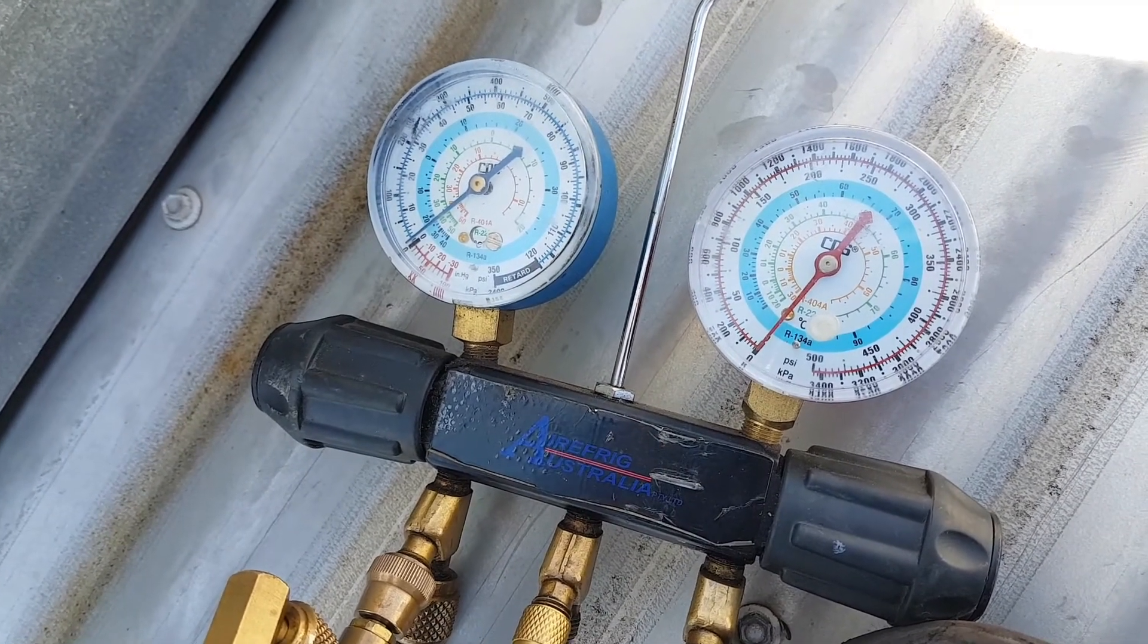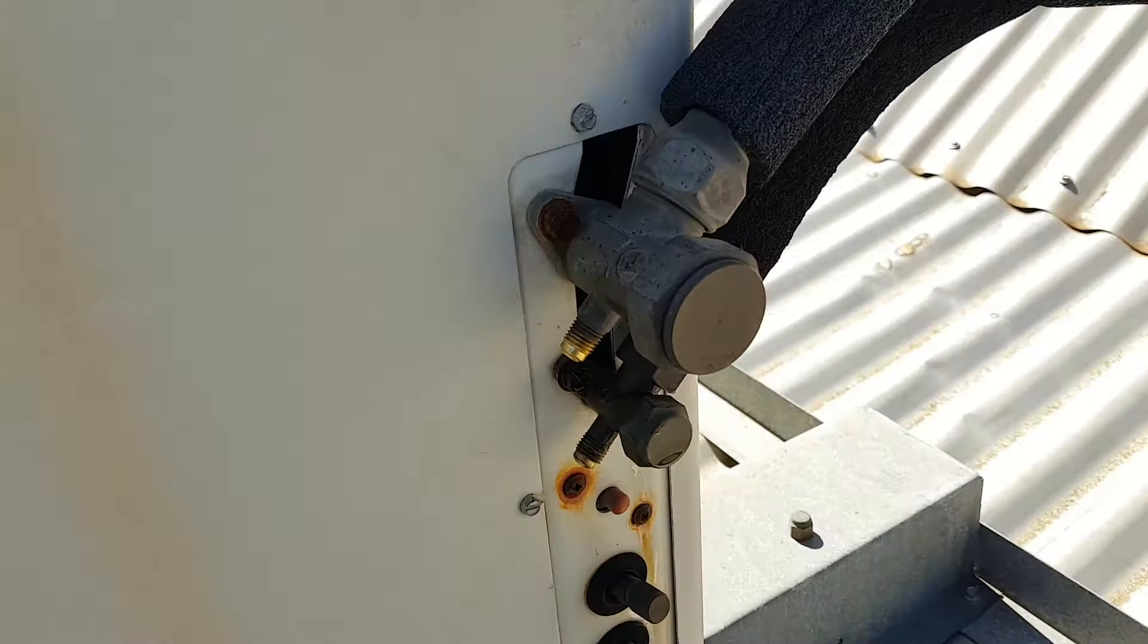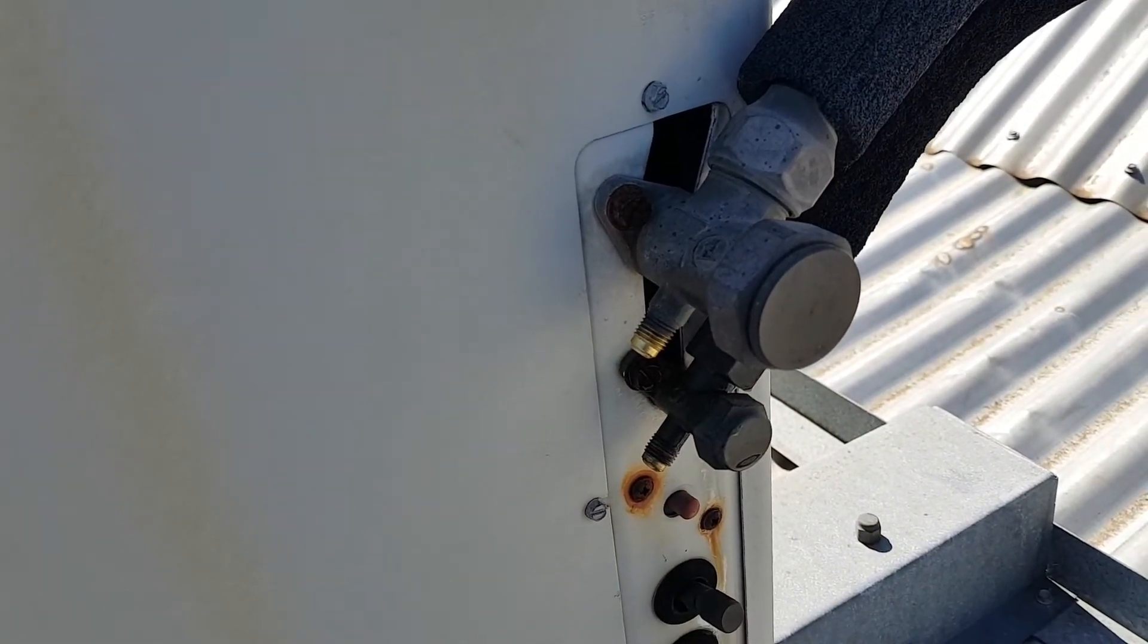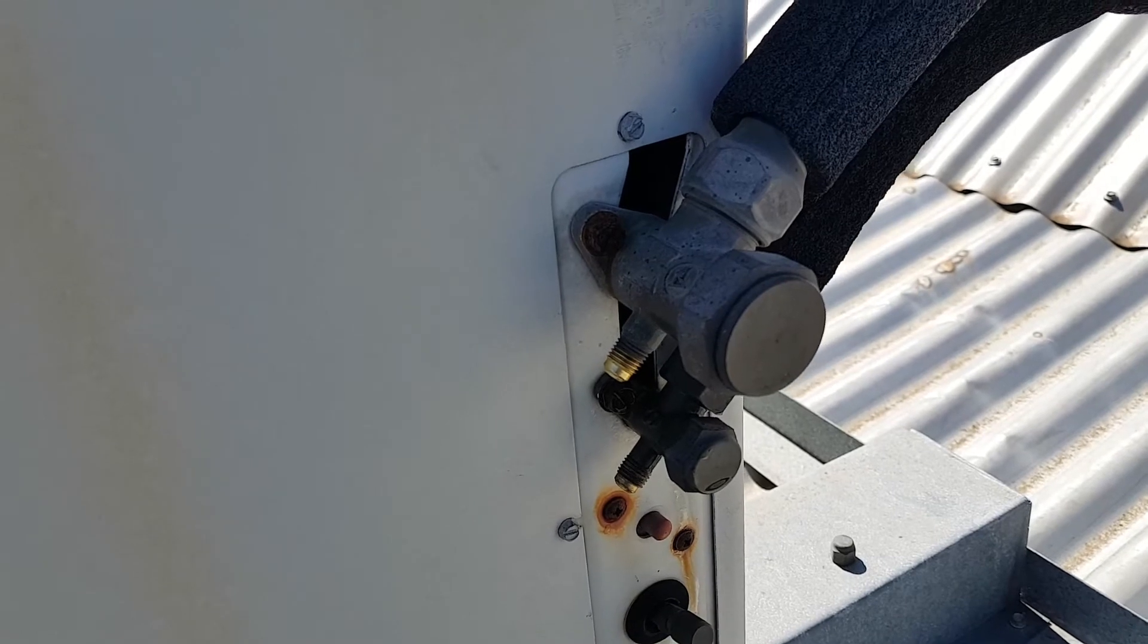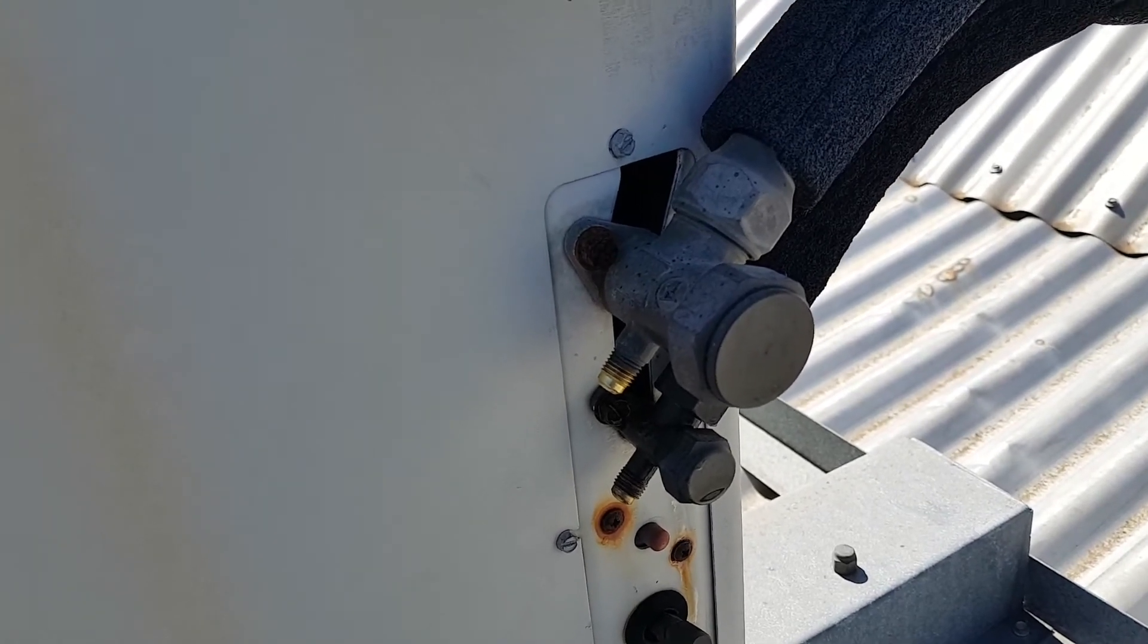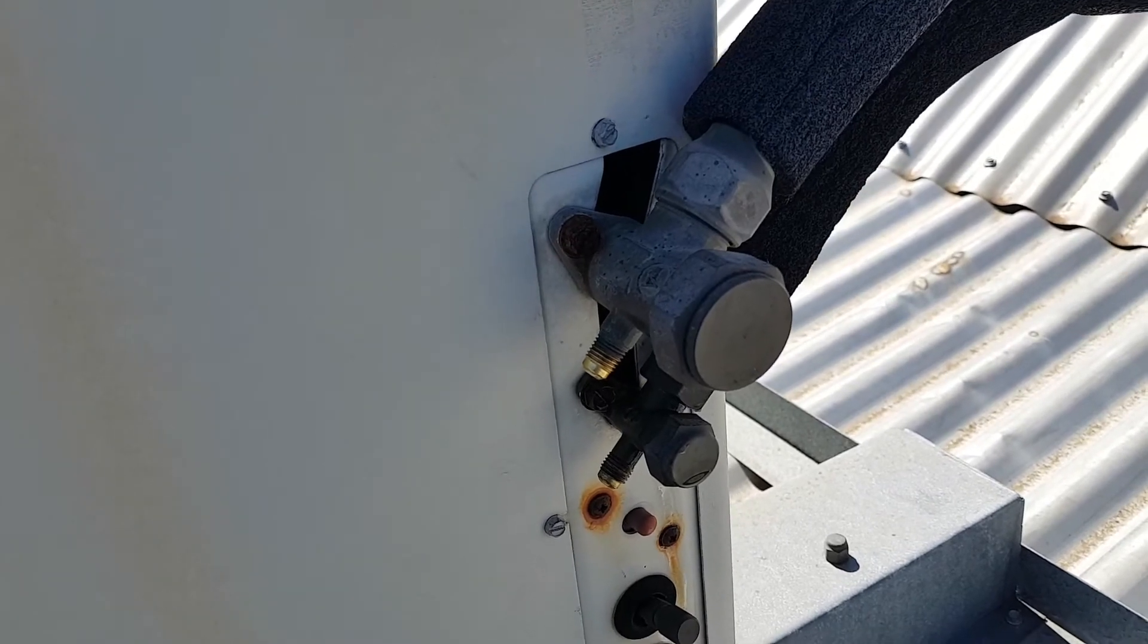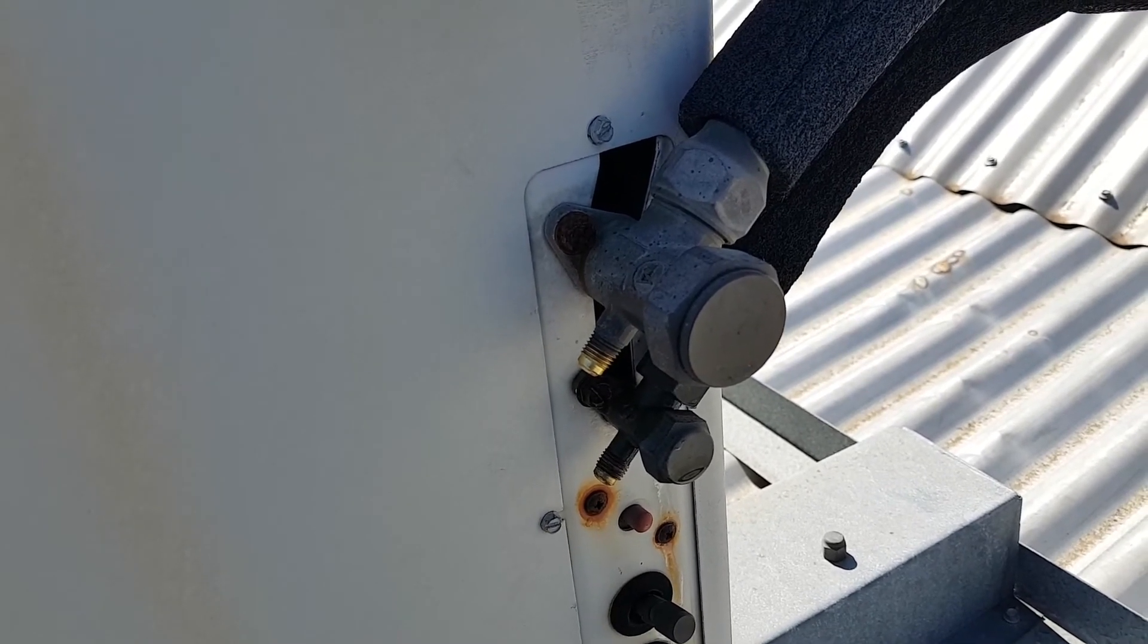This is an old unit on R22 refrigerant. It's hardly going to be worth it by the time you put in a few kilos of refrigerant, find the leak, fix it—all the labor required and materials. It's an old unit, 20+ years old. Technology has moved on a long way now, so it's more cost-effective just to put a new system in.